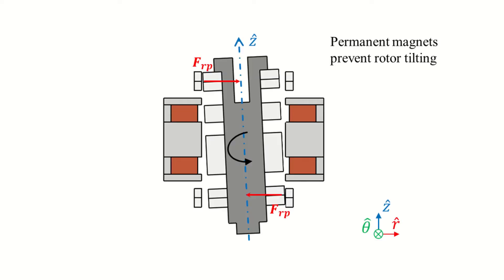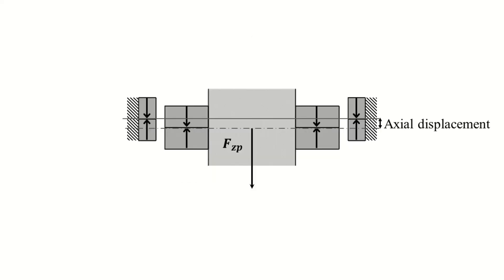When there are radial bearings in opposite ends of the rotor shaft, they also prevent rotor tilting. This permanent magnet configuration also generates an unstable force along the axial direction. If the rotor is displaced along the z-axis, the repulsive force pushes the shaft farther away from the center.